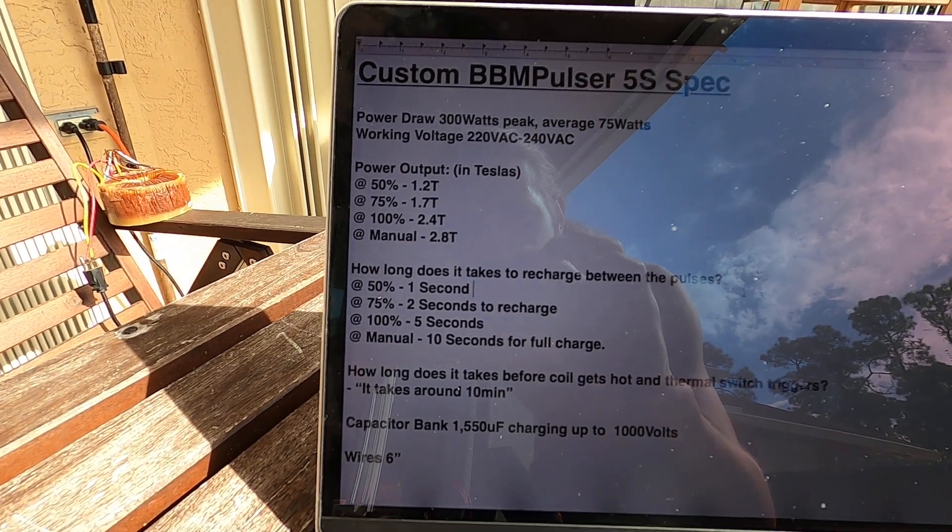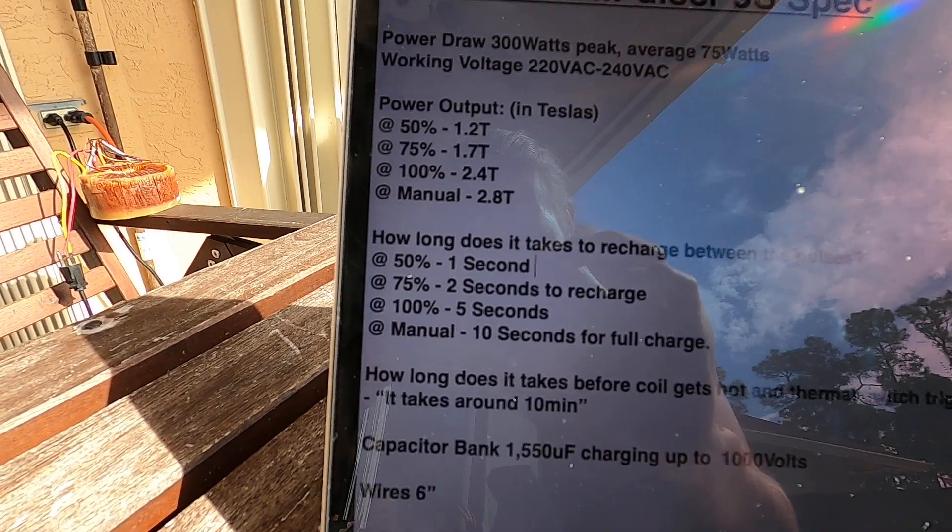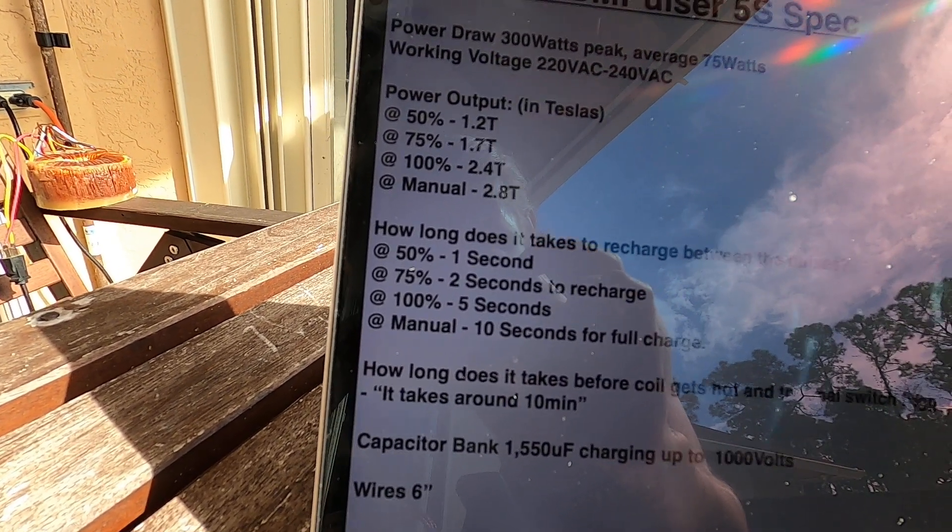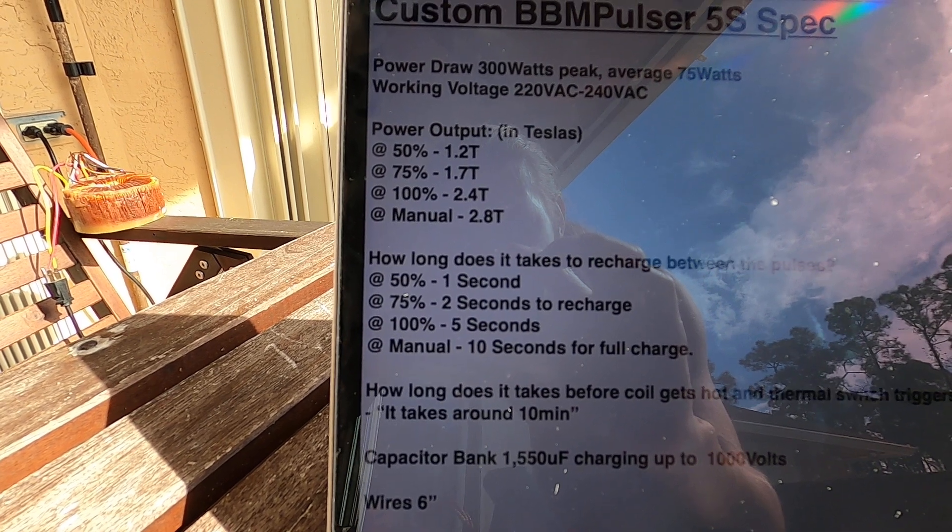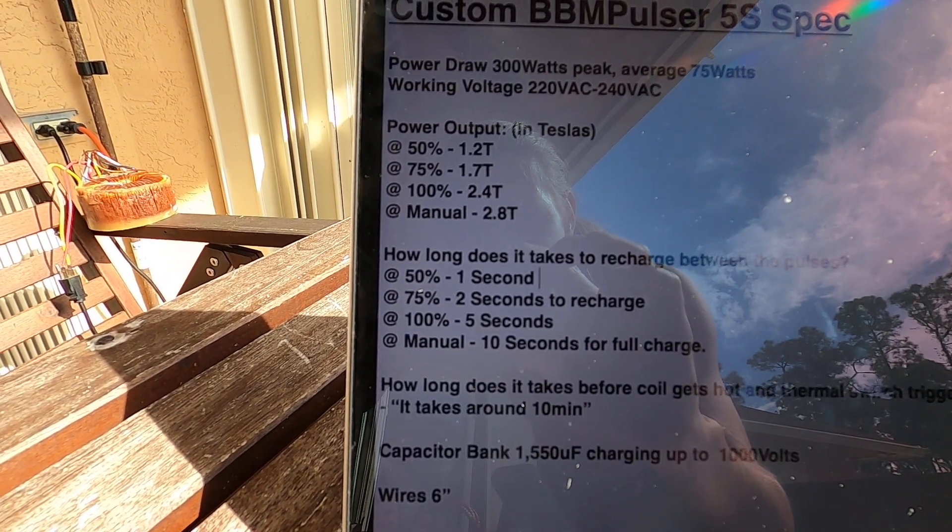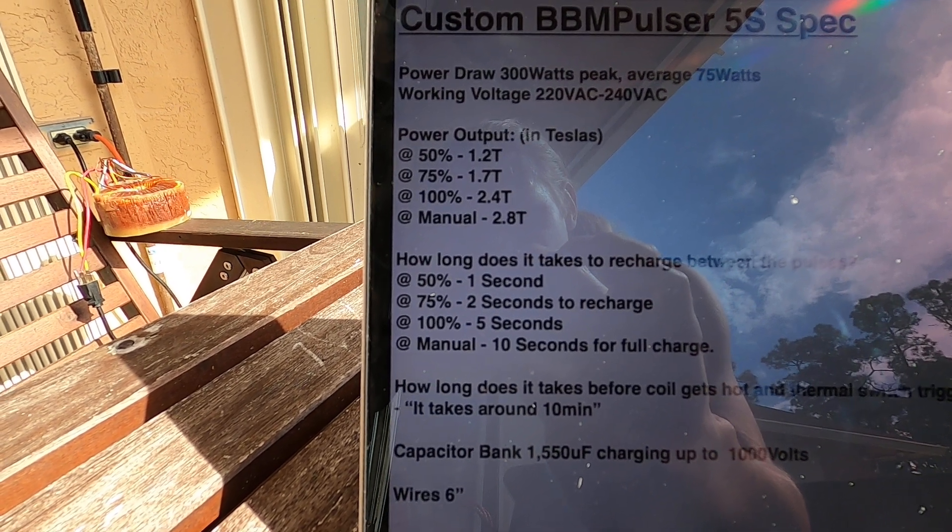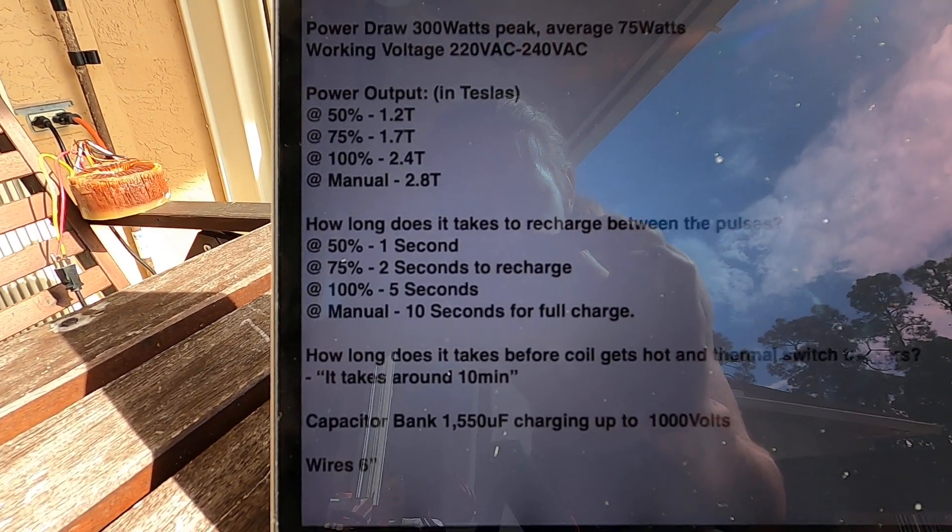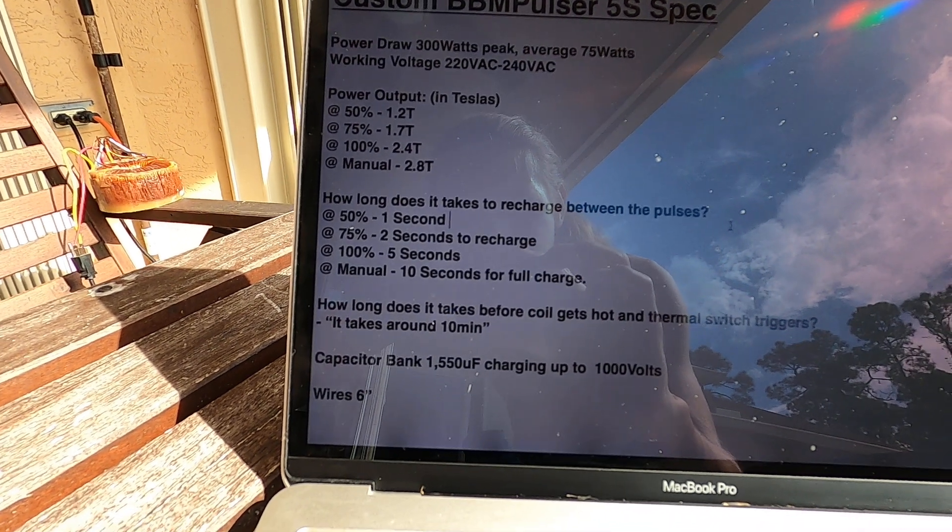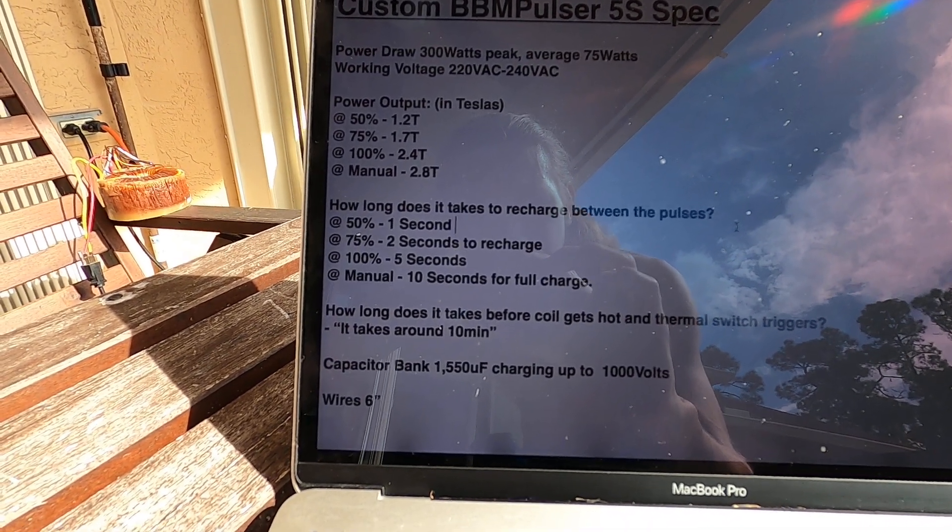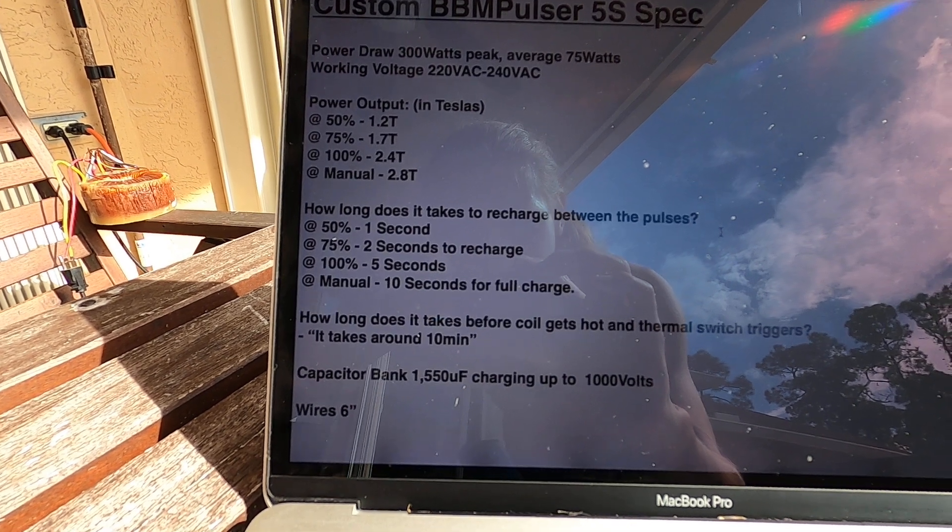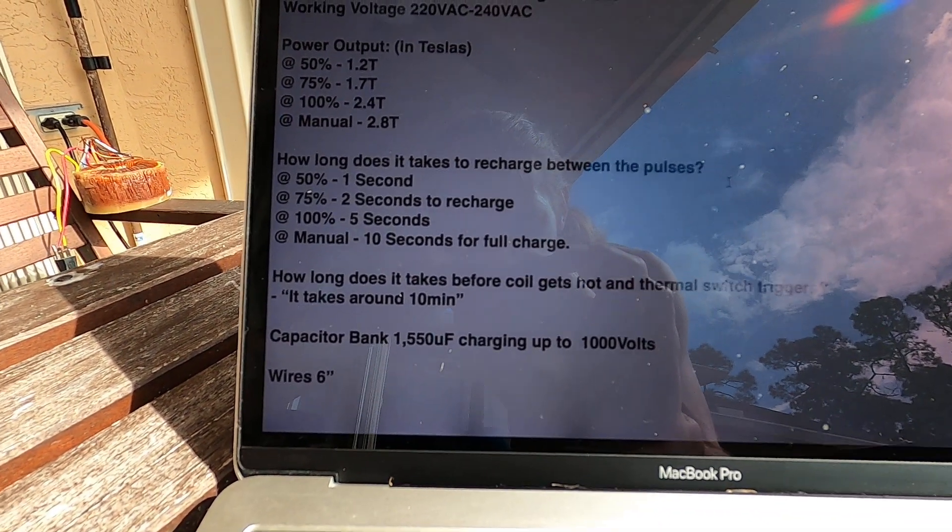How long does it take to recharge between the pulses? Two to three seconds at a hundred percent, takes about five seconds, and manual takes about 10 seconds for full recharge. How long does it takes before coil gets hot and thermal switch triggers? It takes around 10 minutes.